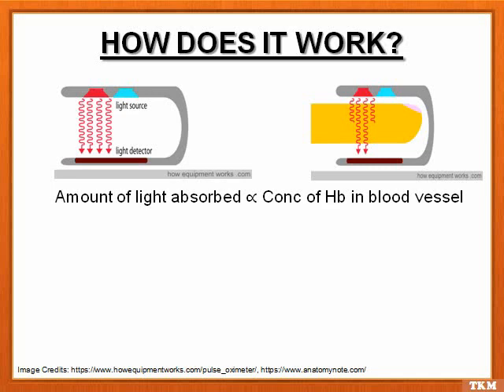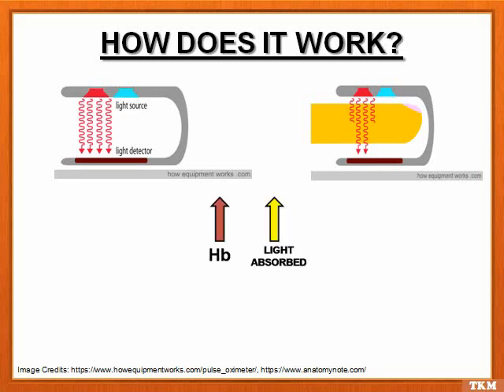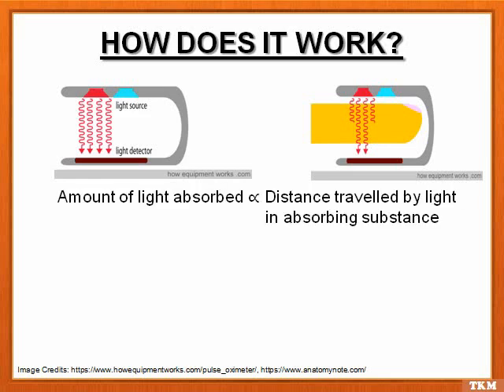So it uses the principle of Beer's law, that is, the amount of light absorbed is proportional to the concentration of hemoglobin in the blood vessels. By measuring how much light reaches the light detector, the pulse oximeter knows how much light has been absorbed. That means the more hemoglobin in the finger, the more light is absorbed. Here it also uses Lambert's law, that is, the amount of light absorbed is proportional to the length of the path that the light has to travel in the absorbing substance.